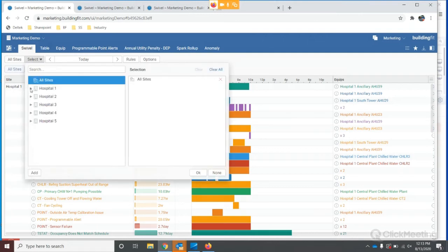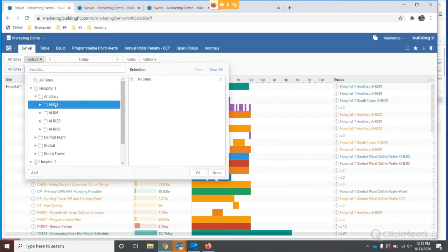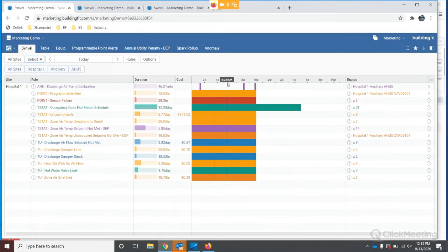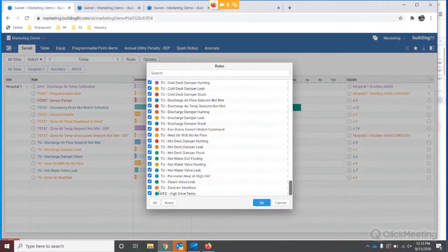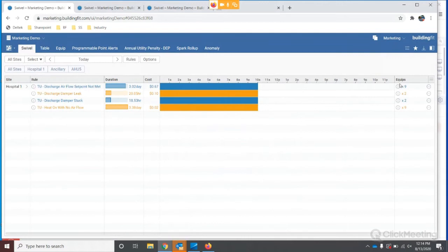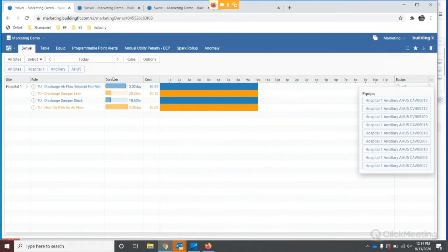Now going back to Air Handler 5 and picking on that again, let's say I'm just concerned with that area of the facility—people complaining a lot in that part of the building. So now we're looking at everything just under that air handler. Drilling down even more specifically, since we have so many rules, we could just look at terminal units and see if any of these rules are triggering. Okay, we've got a number here. In terms of duration, 3.2 days over today—that's obviously more than just a 24-hour or 12-hour period here in the Mountain Time Zone. That means across all these terminal units, we have an aggregate of 3 days of this fault. So if we dig into one specifically...